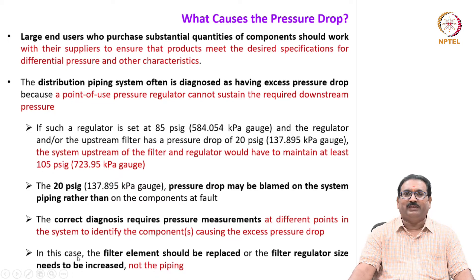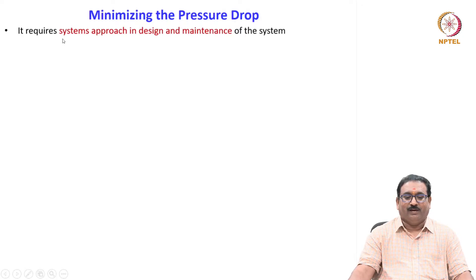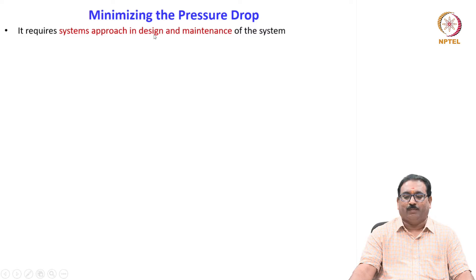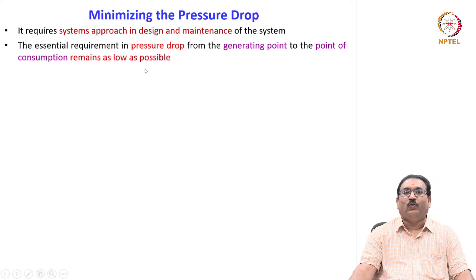In this case, a filter element should be replaced or the filter regulator size needs to be increased, not the piping. Minimizing pressure drop always requires a system design approach and proper maintenance of the system. The essential requirement is that pressure drop from the generating point to the point of consumption remains as low as possible.